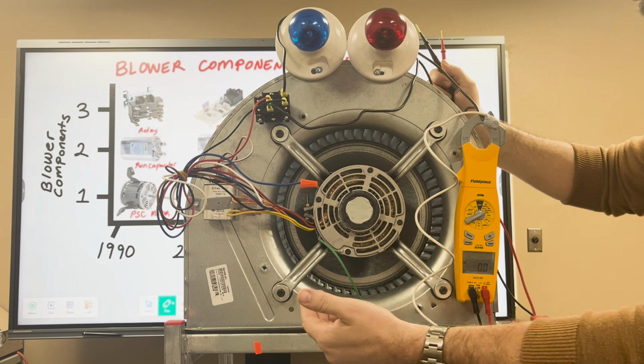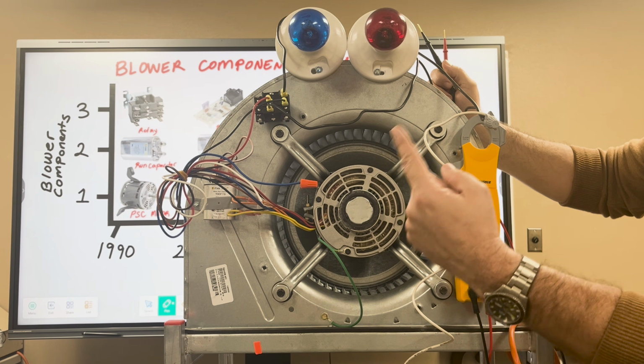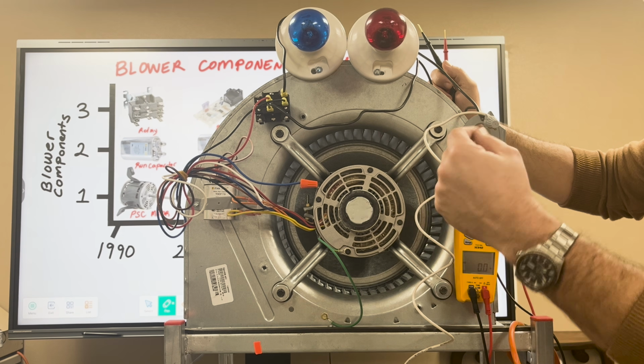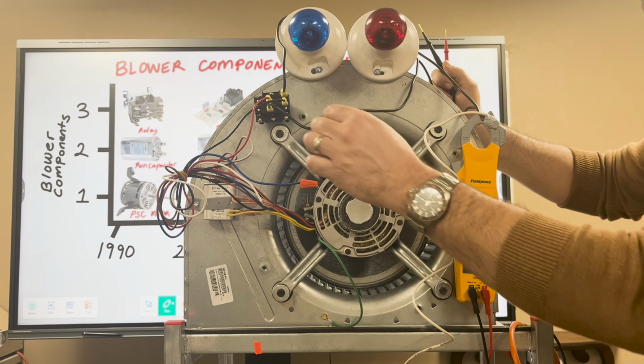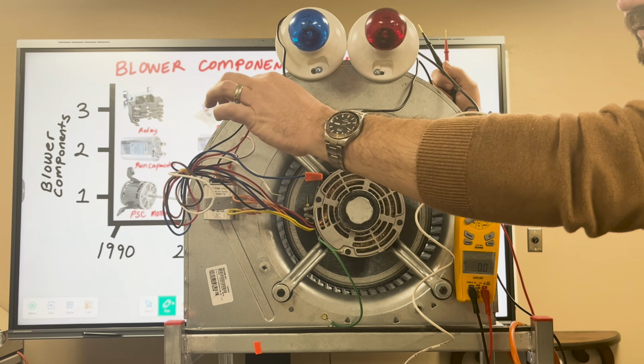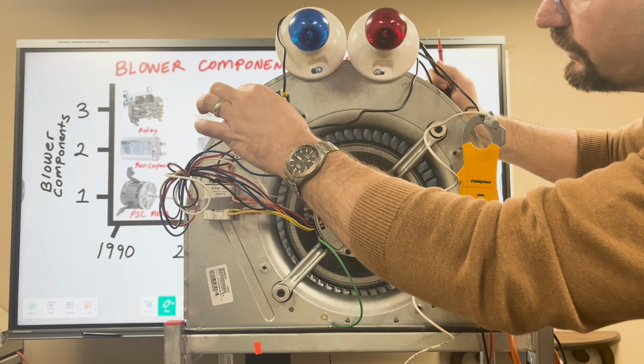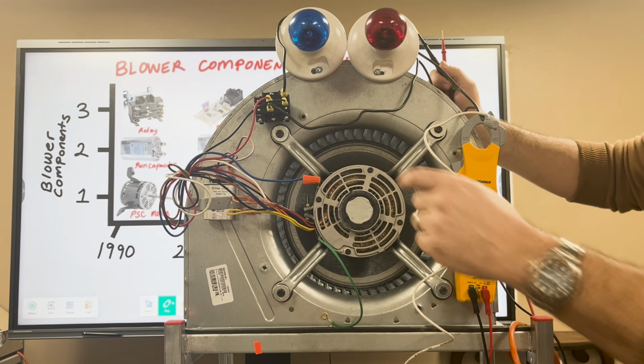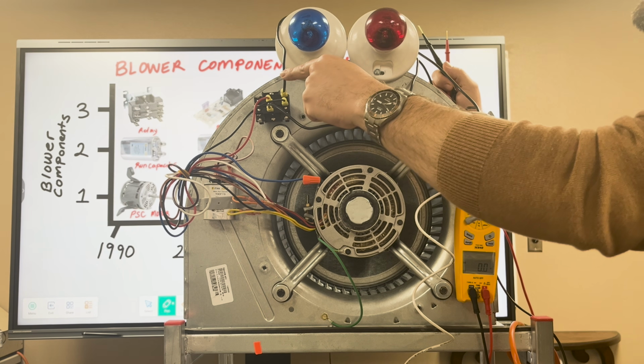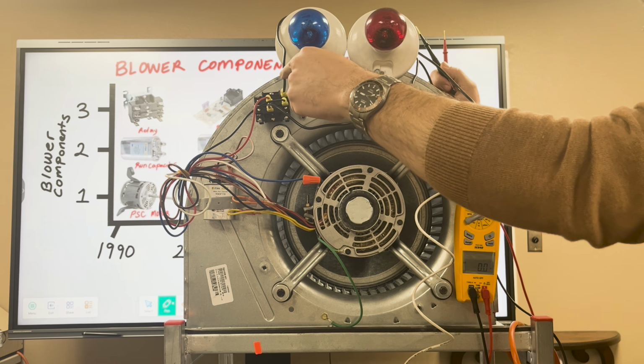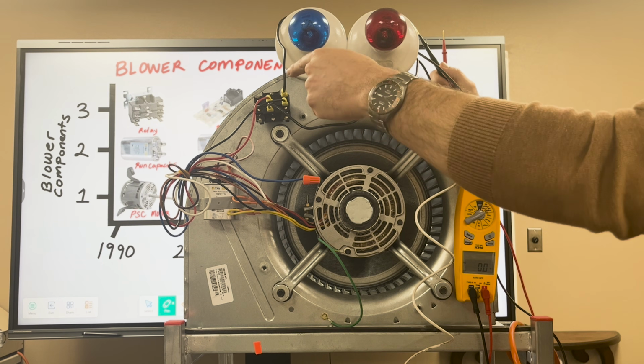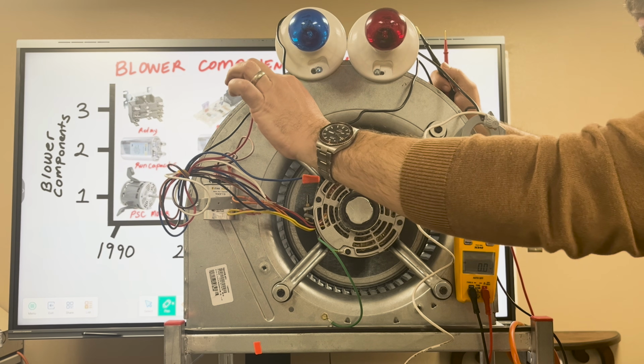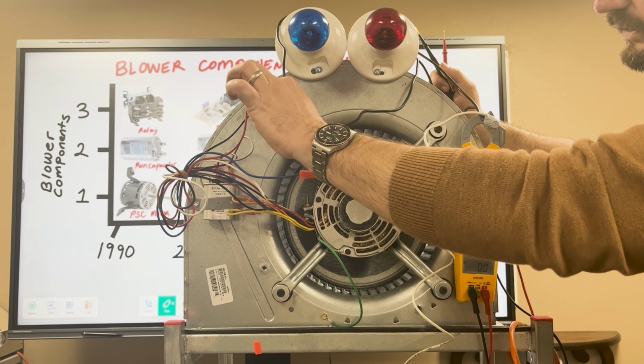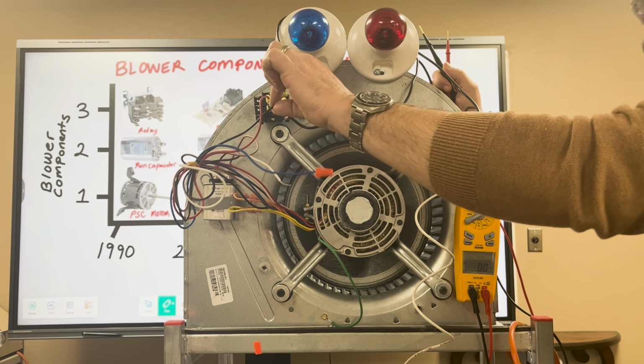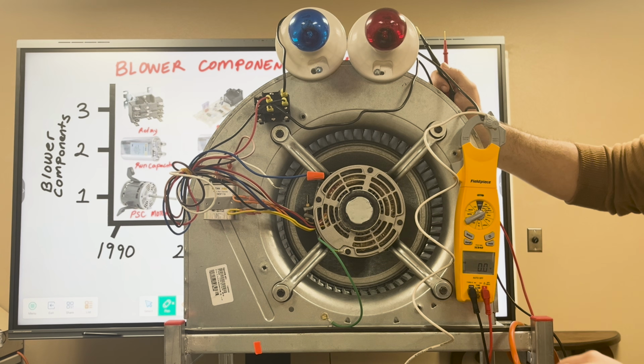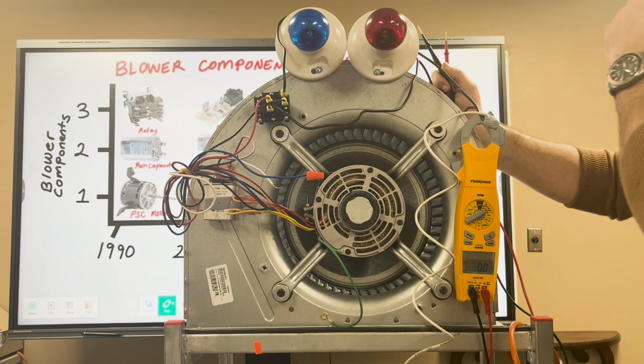I also took the liberty of taking 2 speed taps, red and black, low and high speed, and I have those wired. The red wire comes up to terminal 2, and on terminal 3 I have a light bulb coming over, running off of that. Then on terminal 6 I have my high speed motor winding wired, and my other light bulb wired to that.